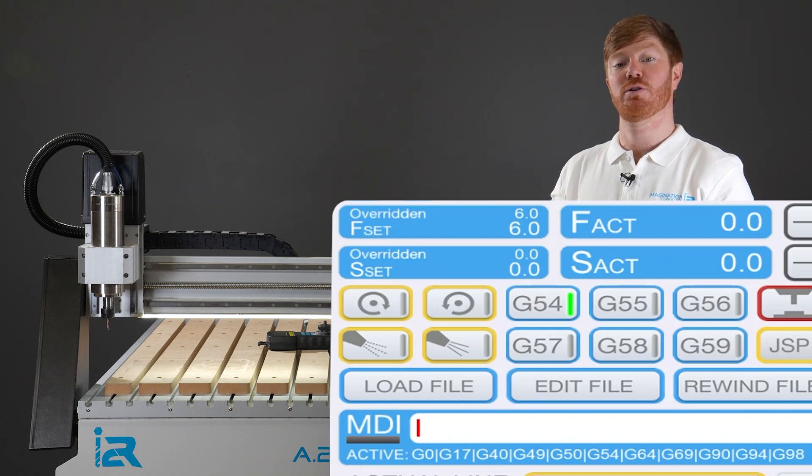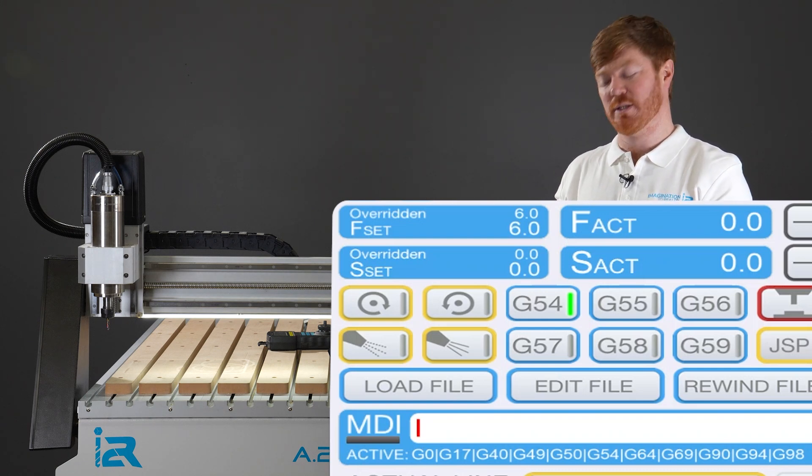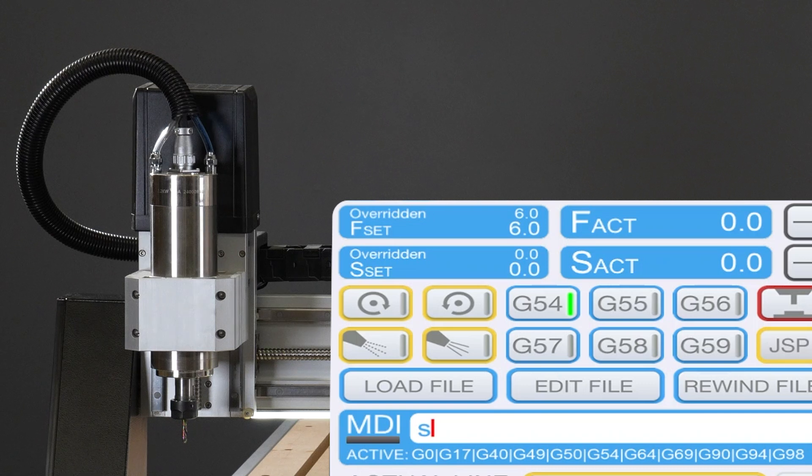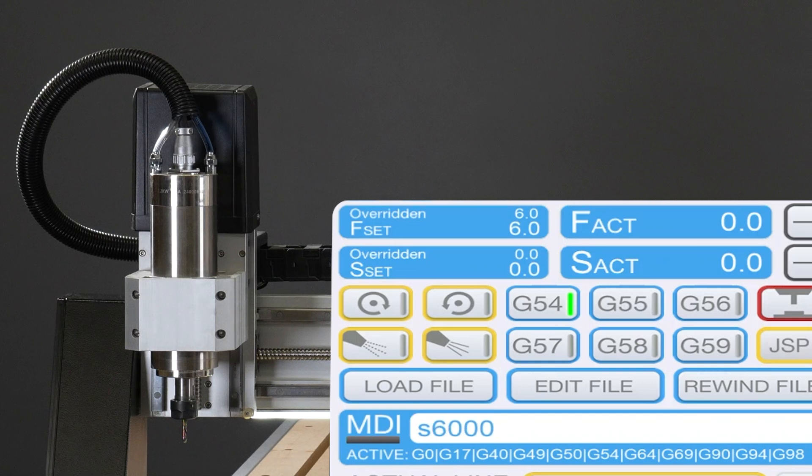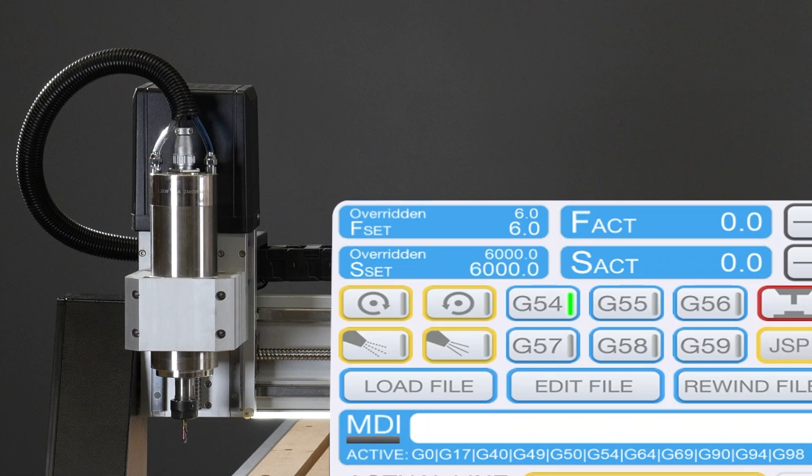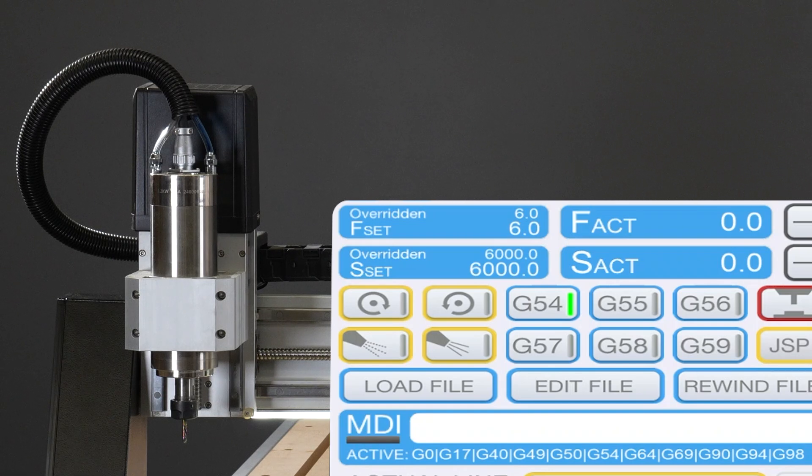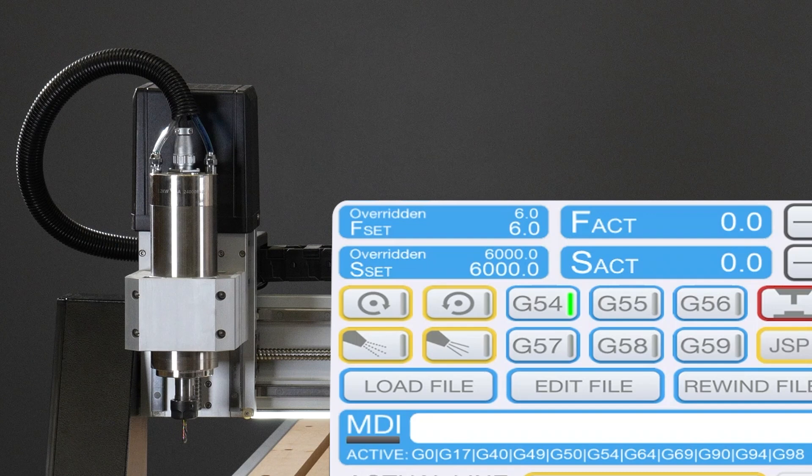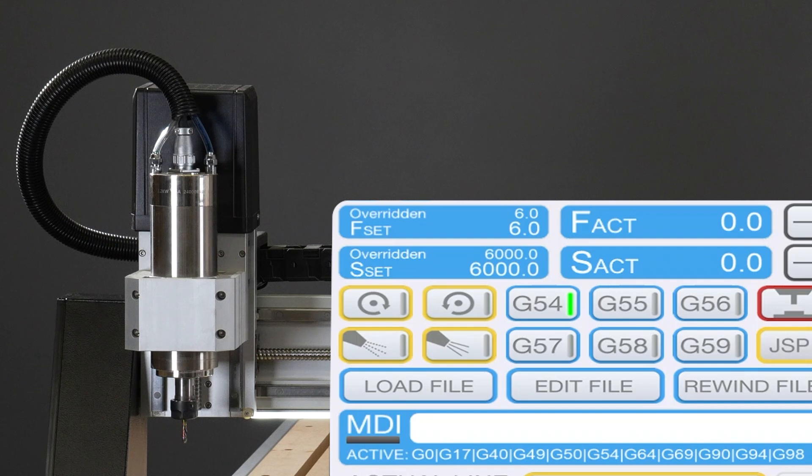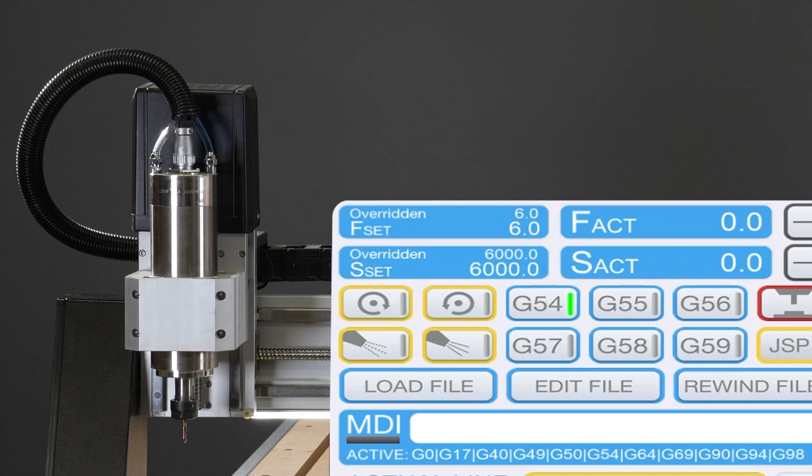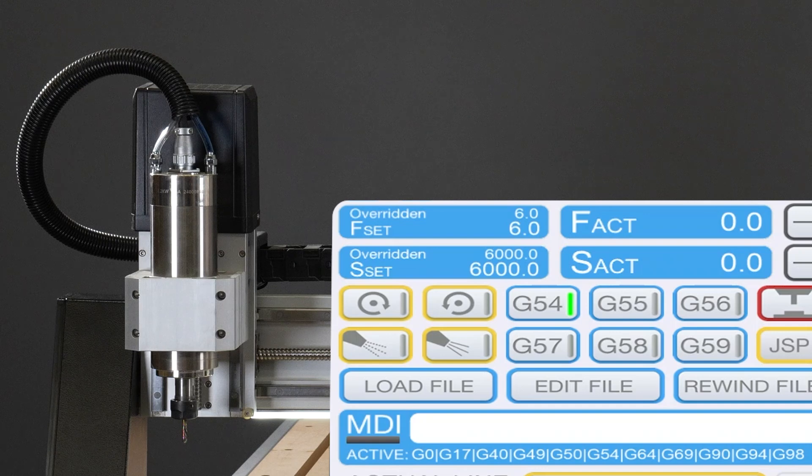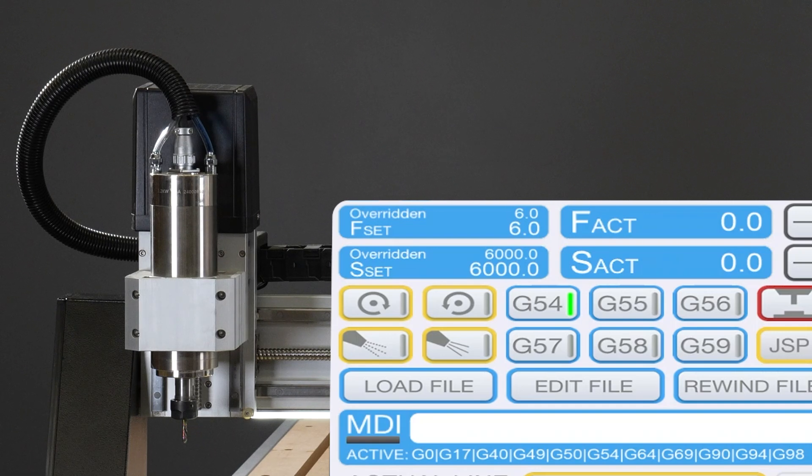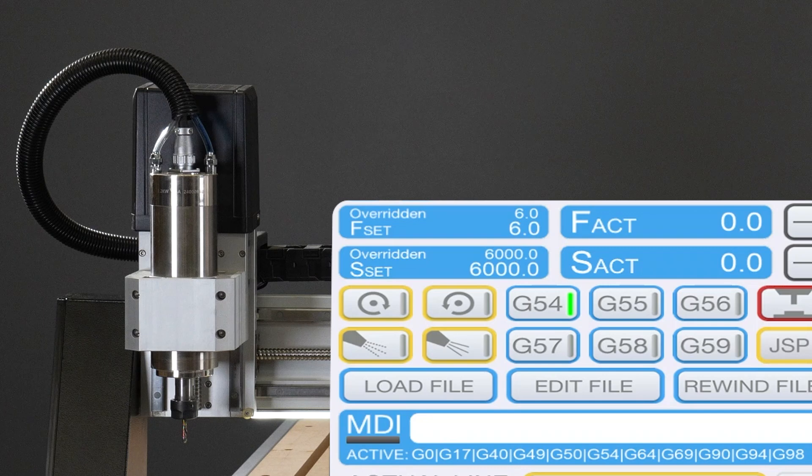We type in S for spindle speed and 6000 and press enter. I recommend you go no lower than 6000 RPM because the spindle prefers to be at a higher spindle speed, and 6000 is something that should help us determine if the spindle is turning or not turning. After entering S6000, you can now see that the S set variable has changed to 6000.